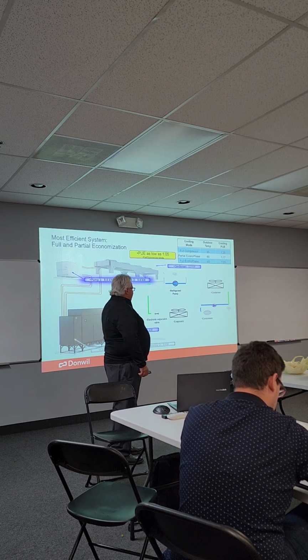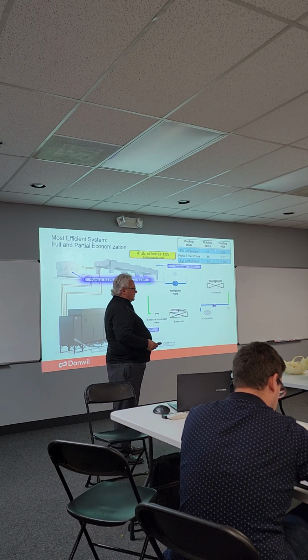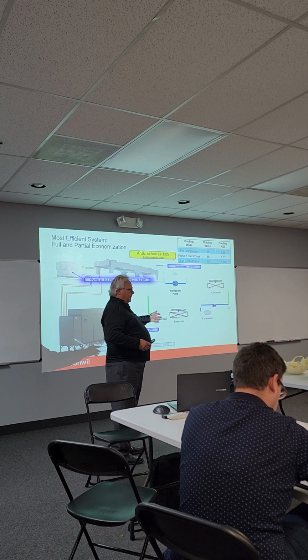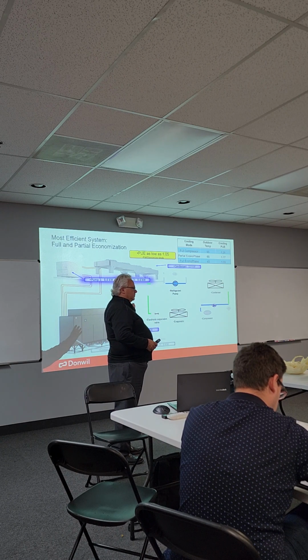We've had more problems with the warranties on those pumps. If you walked over to our shop right now and went in the back room, you'd see a ton of semi-hermetic compressors, a few digital scroll compressors, and none of these pumps.